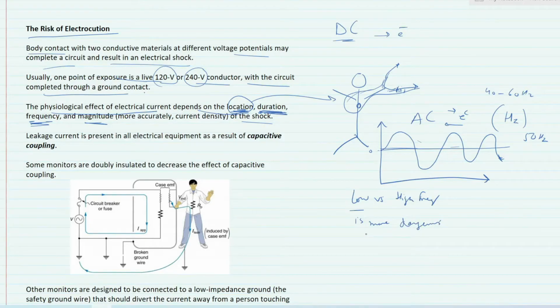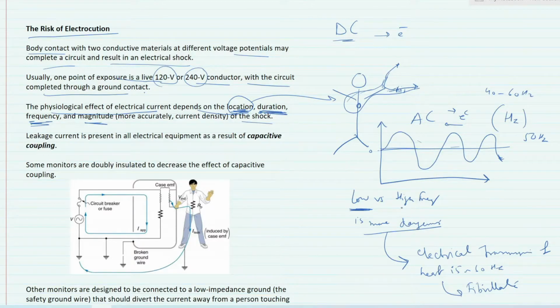Why is low frequency more dangerous? No one knows the exact principle, but some say that the electrical transmission of the heart is close to 60 hertz, and so this can disrupt the functioning of the heart, leading to fibrillation. This is why when we use AC in the human body, as we'll see in surgical diathermy shortly, we have very high frequency AC flow, and this causes burns or cuts by transferring heat to that area.